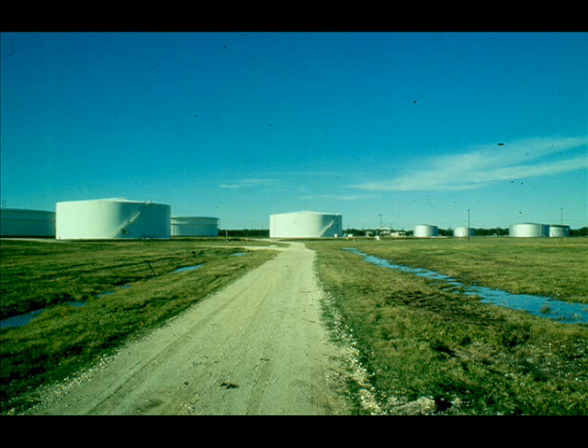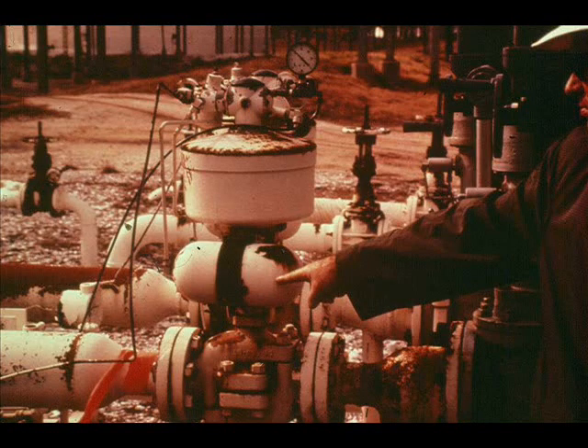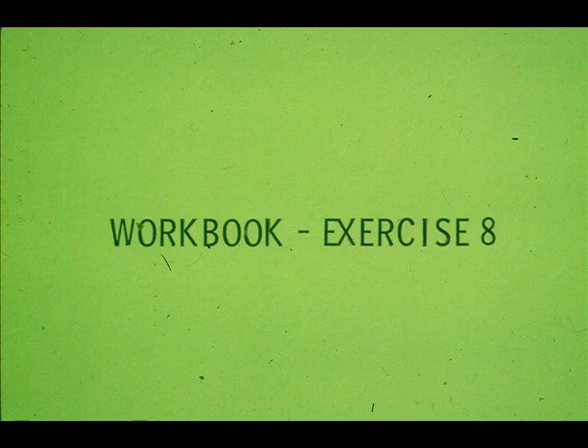A disadvantage in using a piston operator is the need for a source of air supply. This can become a problem in remote locations. In addition, fail-safe capability of a piston operator requires additional hardware, such as these volume tanks. Now, work exercise 8 in your workbook.